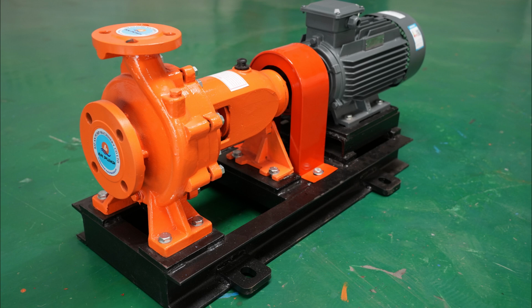First up, vibration analyzers. These are like stethoscopes for pumps. We can actually listen to the internal vibrations, to hear what's happening inside. They measure the frequency and amplitude of the vibrations, which can tell us a lot about the pump's condition. Different problems create different vibration patterns. A worn bearing will have a different vibration signature than, say, an unbalanced impeller. So we're decoding the secret language of vibrations.